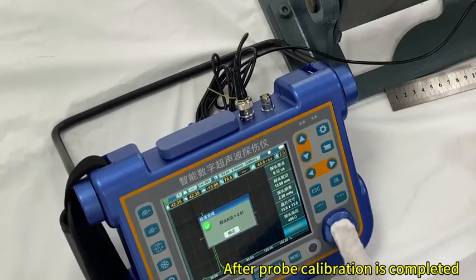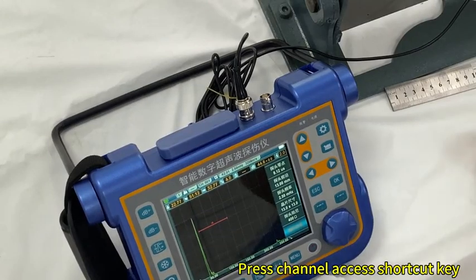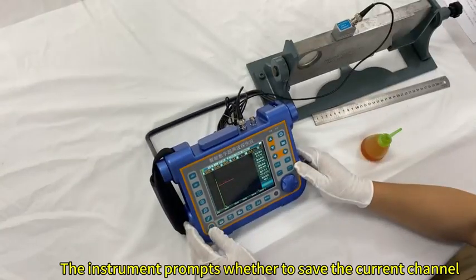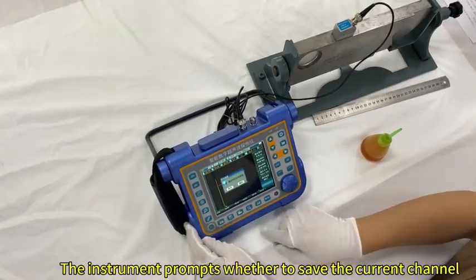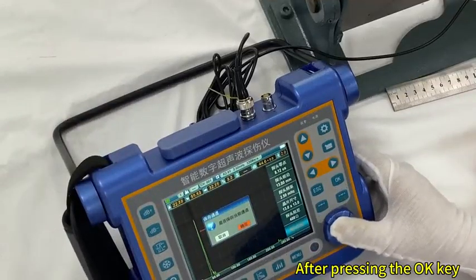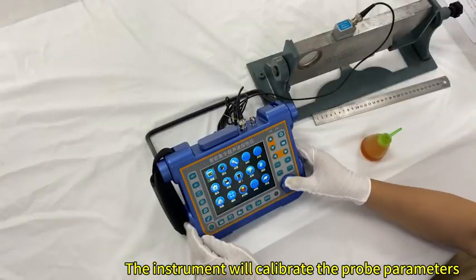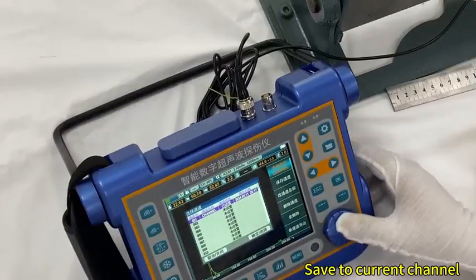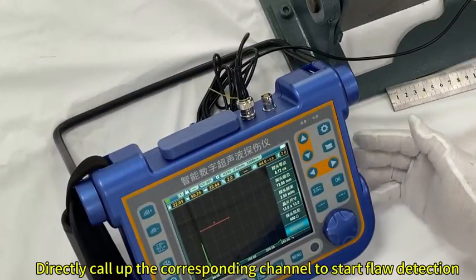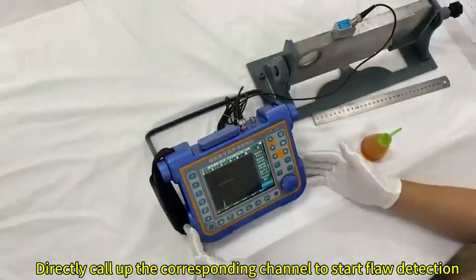After probe calibration is completed, press the channel access shortcut key. The instrument prompts whether to save the current channel. After pressing the OK key, the instrument saves the calibrated probe parameters to the current channel. For future use, directly call up the corresponding channel to start flaw detection.